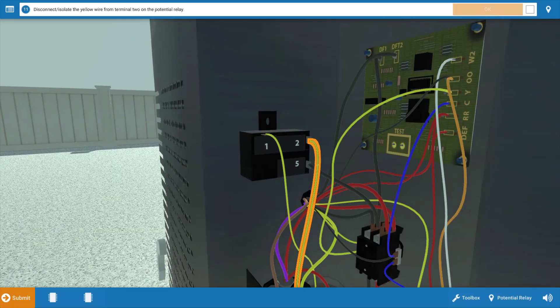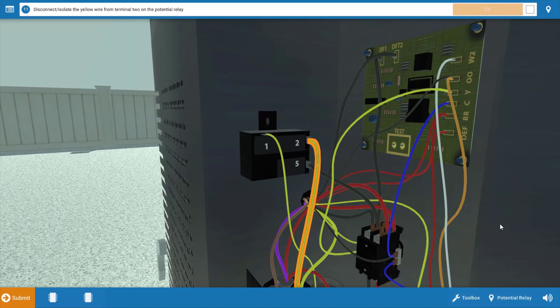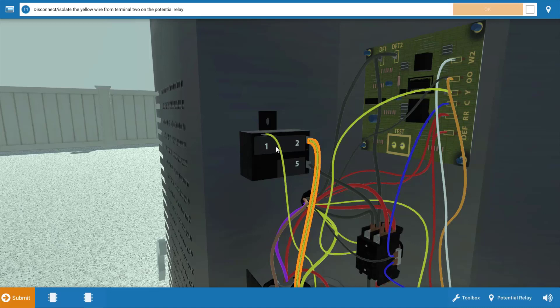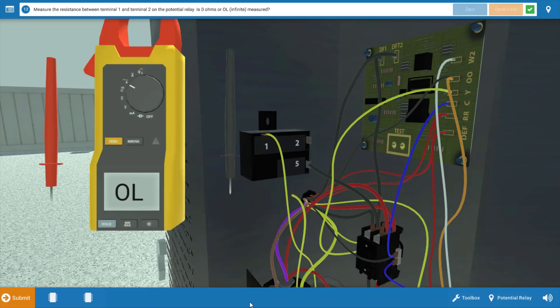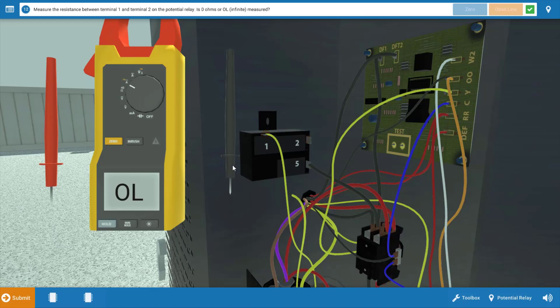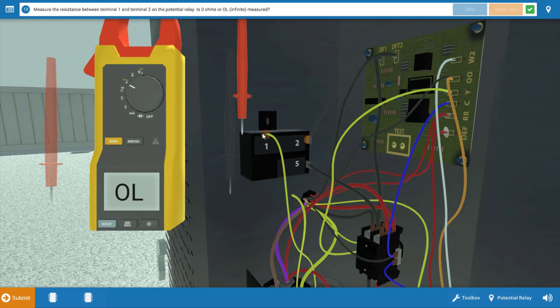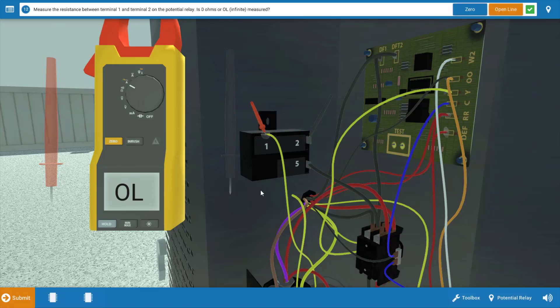And we're going to start with the potential relay. Now, it doesn't matter where you start here. You can start by checking the capacitors if you want. But the potential relay seems like the easiest place to start. We need to isolate it. So we're going to click on this wire on terminal 2. And we're just going to disconnect the wire from there so the contacts are isolated. Next, we're going to measure for resistance across the contacts or between terminals 1 and 2. Now, since they're normally closed contacts, we should obtain a reading of 0 ohms. So let's place our leads at the glowing orange hotspots and measure resistance across those isolated contacts. And when we do this, we see we have infinite resistance or OL on the meter.